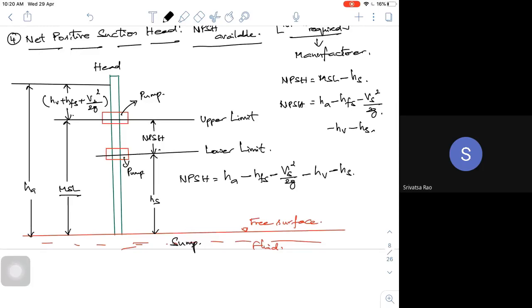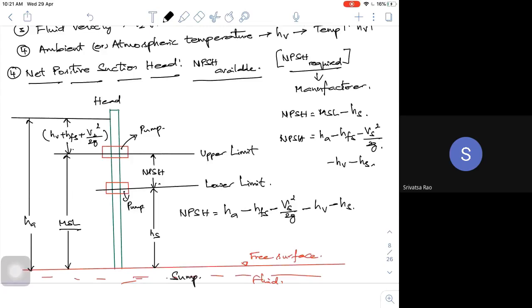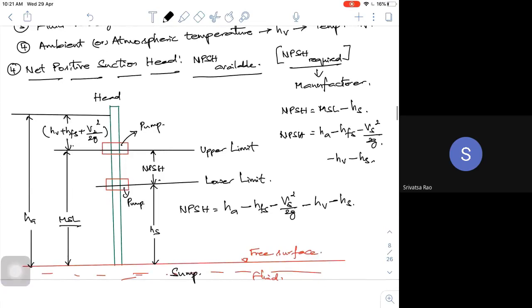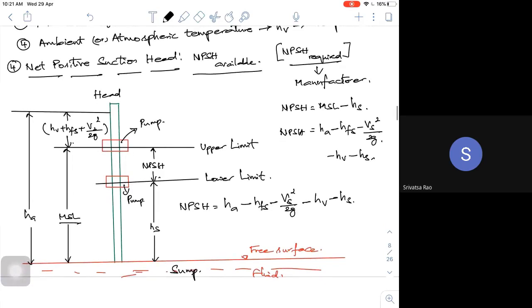Okay. Now, NPSH required is calculated by the manufacturer. With some methodology, the manufacturer puts a standard design pump under different conditions, plays with this MSL, and comes up with a number, telling that the pump will work efficiently without any malfunction between this height.